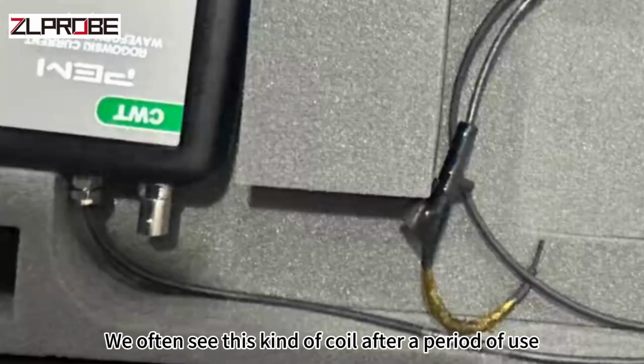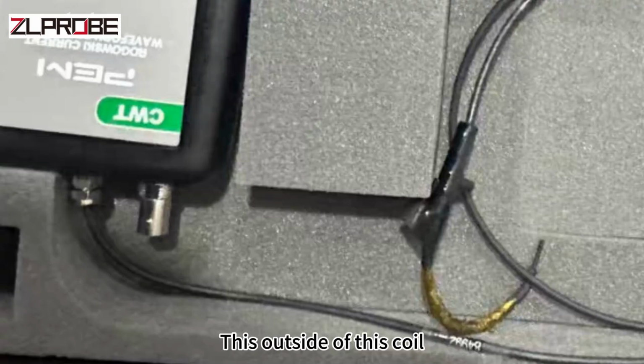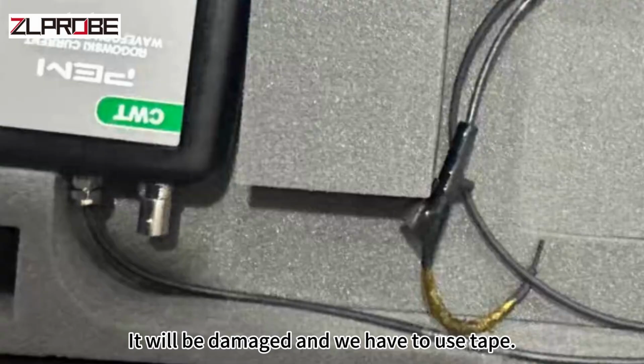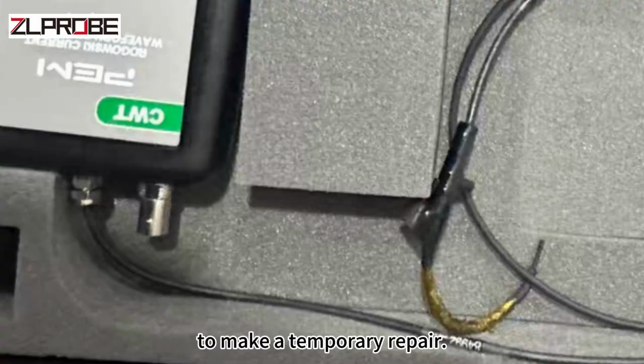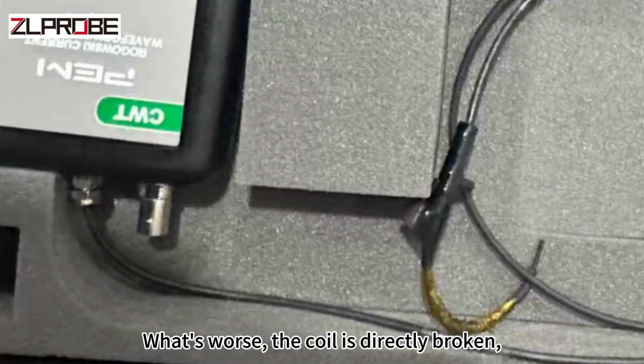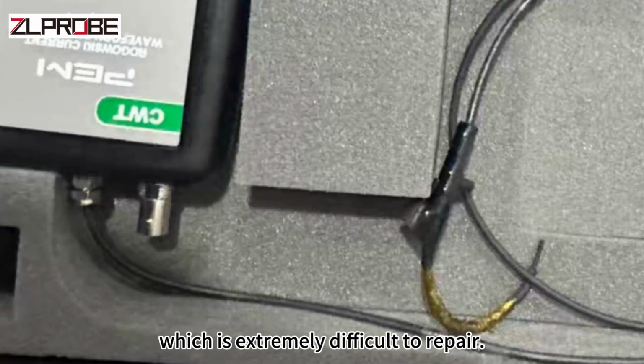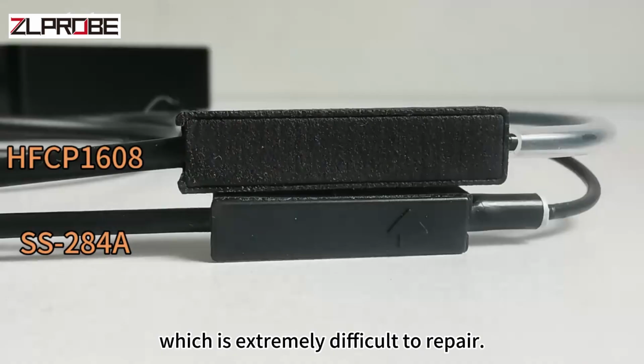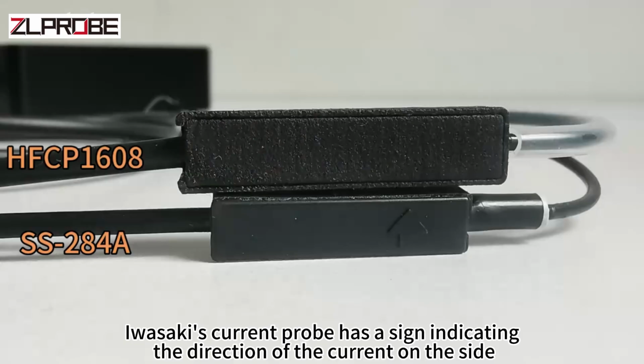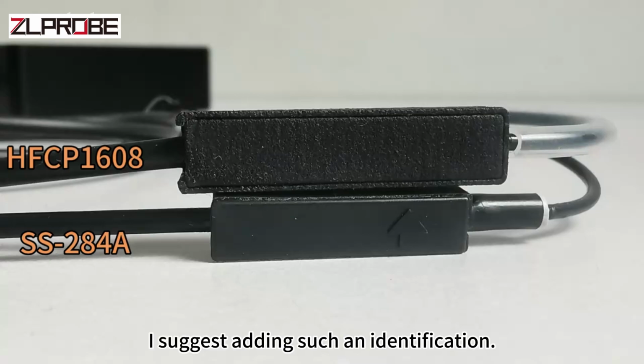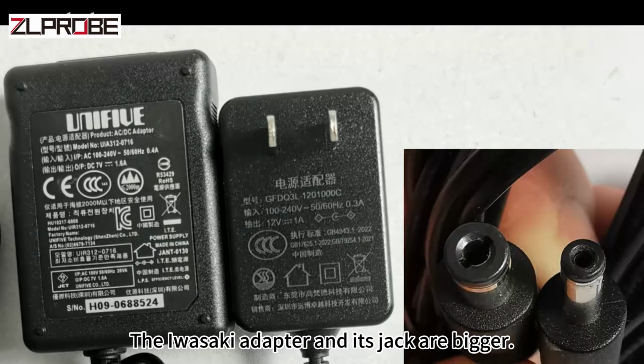We often see this kind of coil after a period of use. The outside of this coil, the insulation, will be damaged and we have to use tape to make a temporary repair. What's worse, the coil is directly broken, which is extremely difficult to repair. Iwasaki's current probe has a sign indicating the direction of the current on the side, while this probe does not have one. I suggest adding such an identification. The Iwasaki adapter and its jack are bigger.